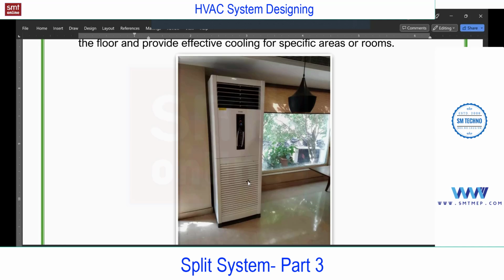We cannot move it after installation. Once you install, the copper pipe you can find at the back side of the unit is going to run towards the outdoor and connect the same as the high wall. The only difference is that in the high wall, we place the FCU on the wall, and this is the tower type, the floor mounted.